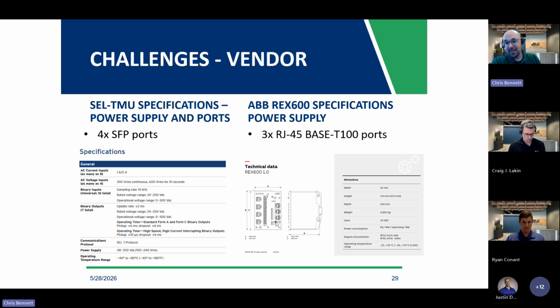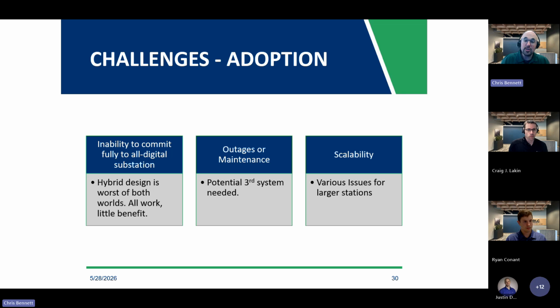The ABB REX600, for instance, for the merging unit, will only provide you 3 RJ45 base T100. Now that means that it is a fixed copper wiring solution that it's expecting for Ethernet cable. The issue here is that we may have interference, we may have a distance problem, we may need a separate fiber converter. So depending on your application, some vendors might be better than others. You may be stuck with a vendor, like Craig was mentioning, ABB is a little bit more flexible with their relay and the backup, but you also may have a physical limitation on the actual design side. So some of the challenges to be aware of.